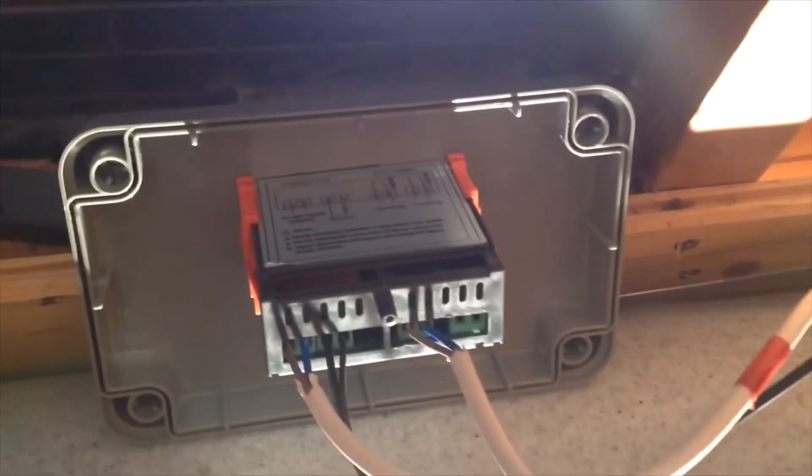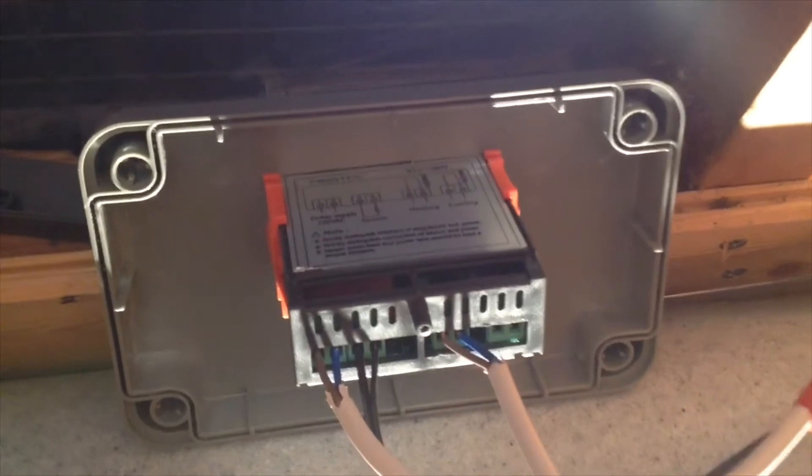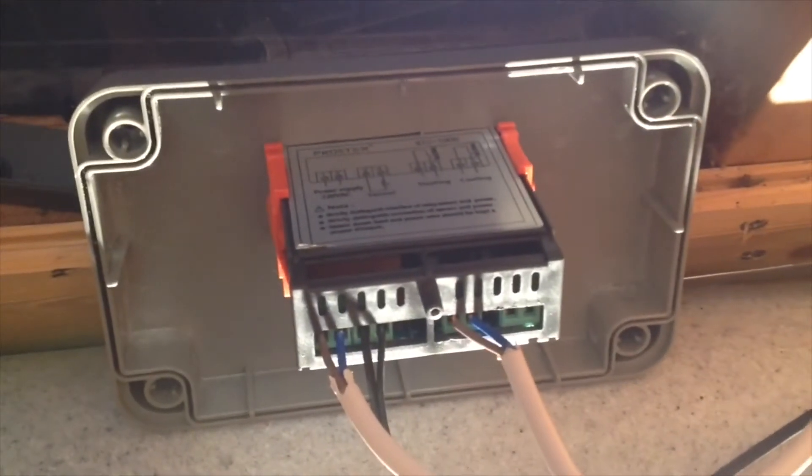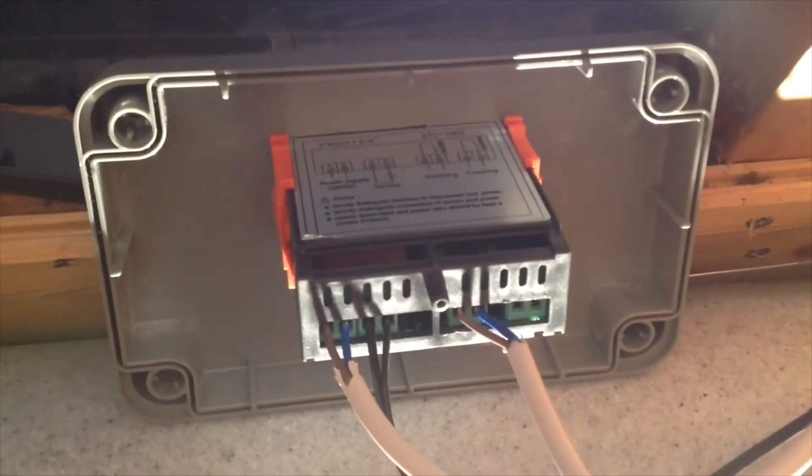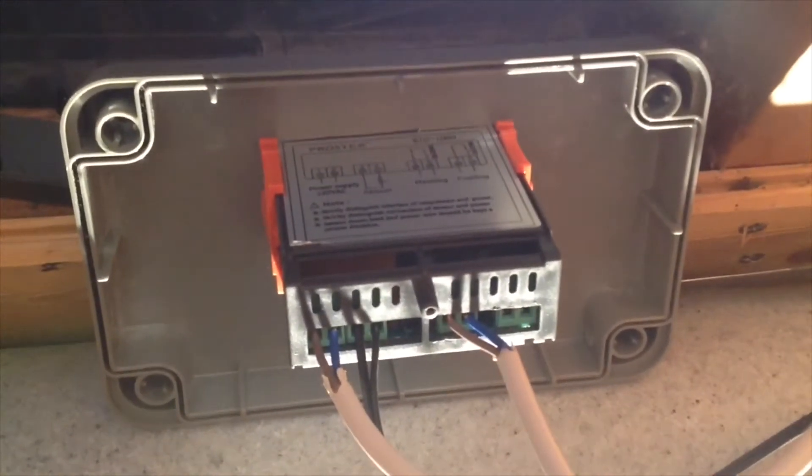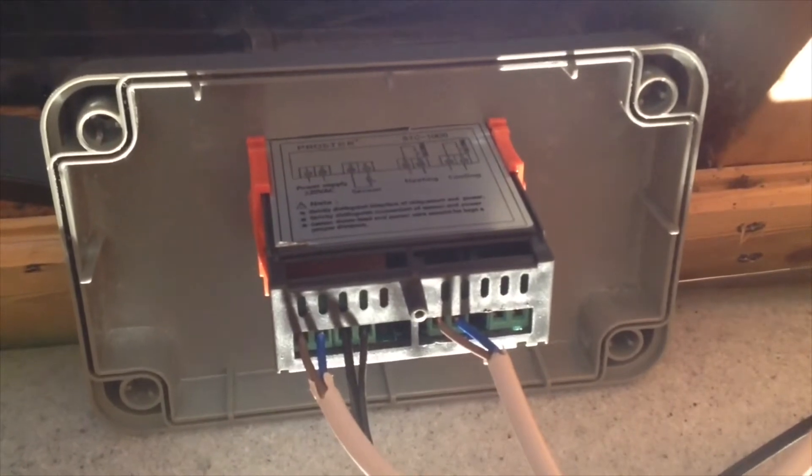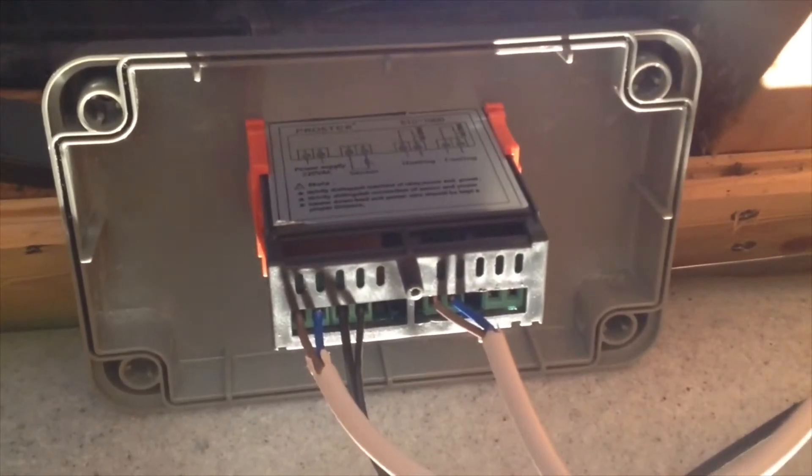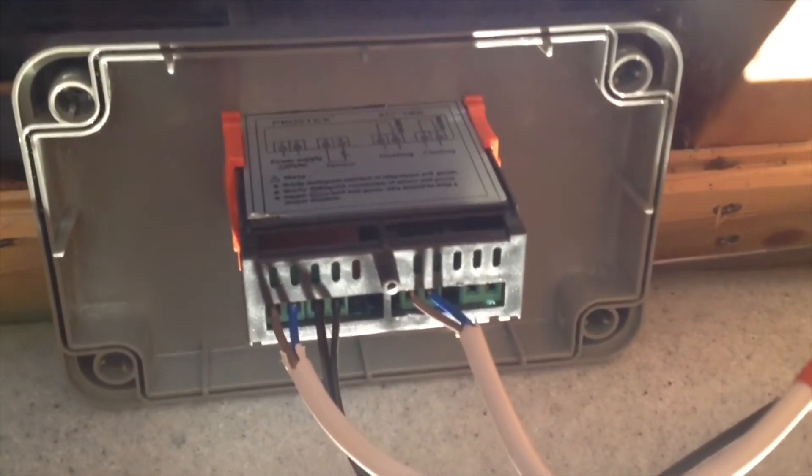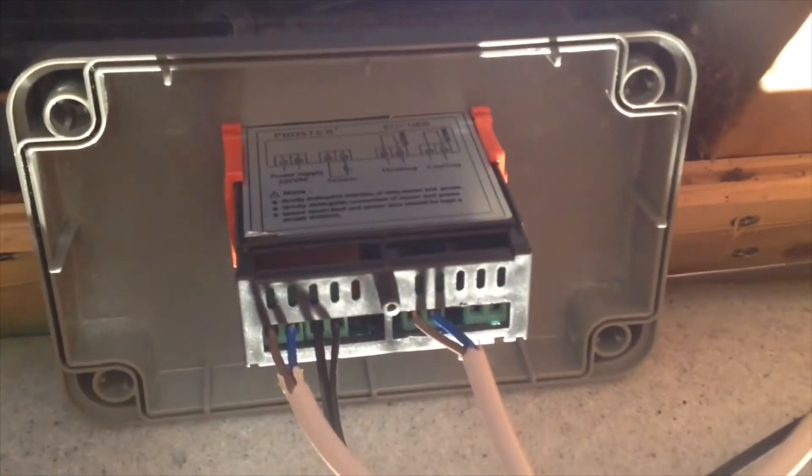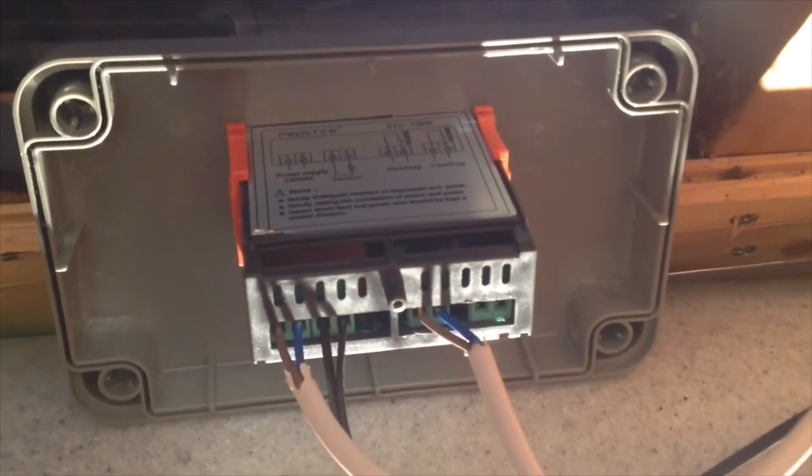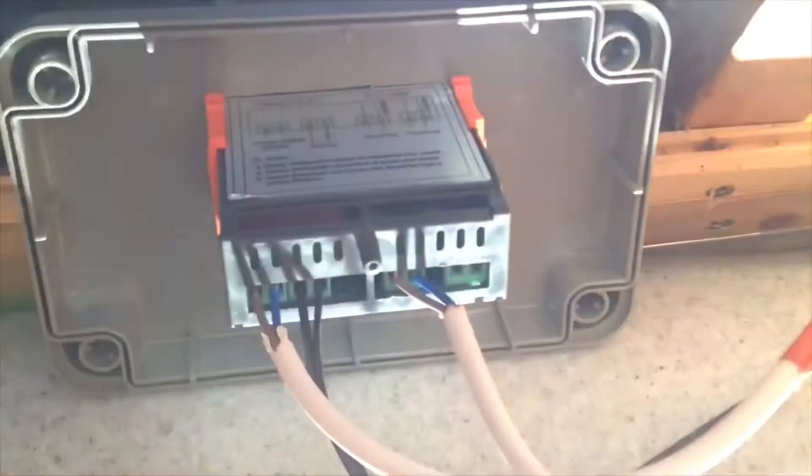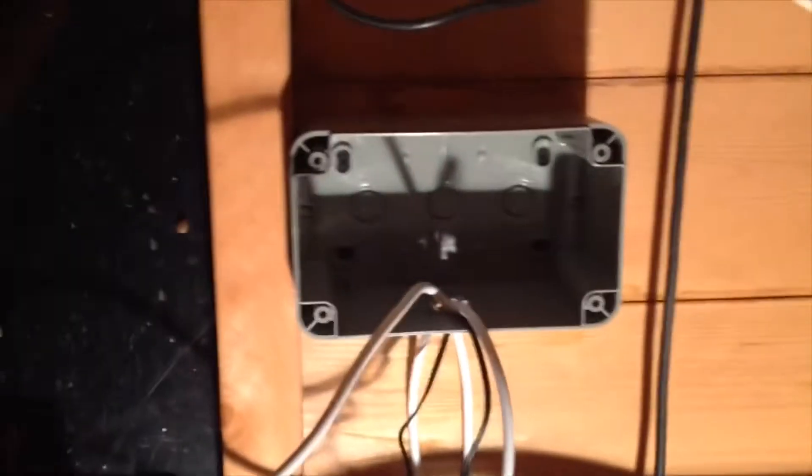Okay, so I'm wiring up the controller and you've got on the far left there, you've got power supply, live then neutral, then you've got the probe which you can put in any direction, and then you've got the heating going to the heating relay, live and then neutral.